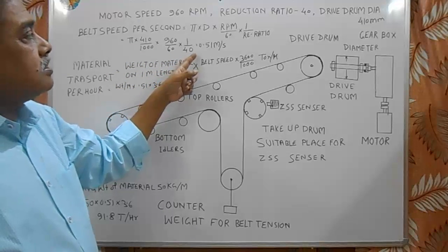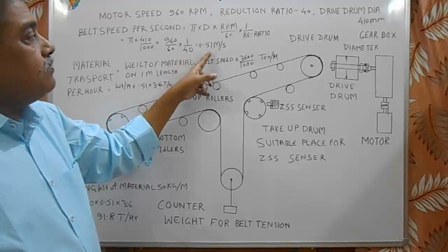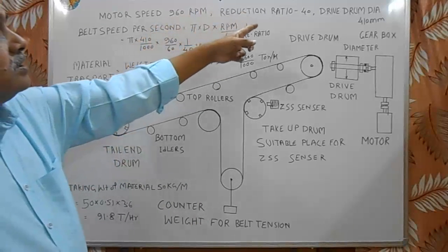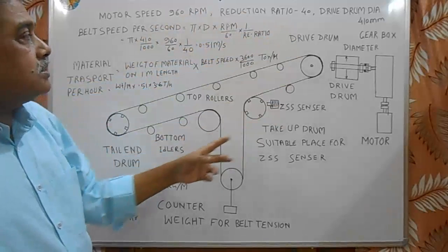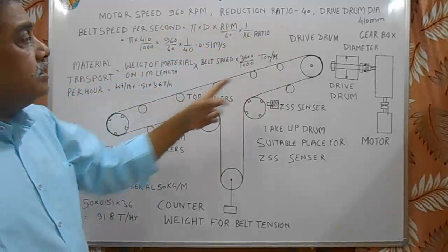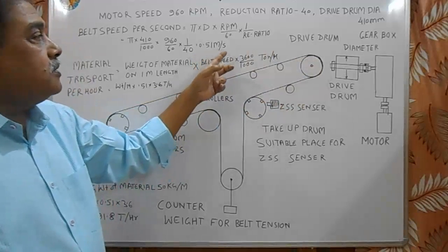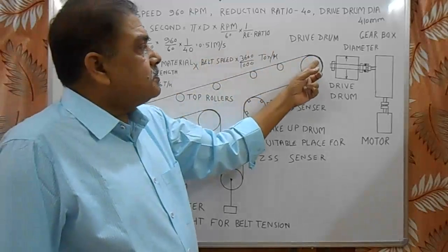It is equal to 0.51 meters per second. This means with this motor of 960 rpm, reduction ratio of gearbox 40, and drive drum diameter 410, the linear speed of drive drum surface is 0.51 meter per second and the belt speed is same as the linear speed of drive drum.